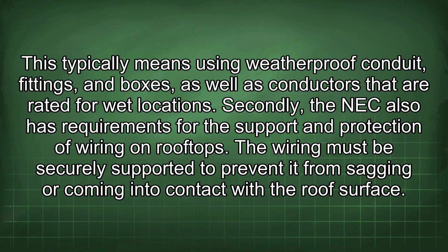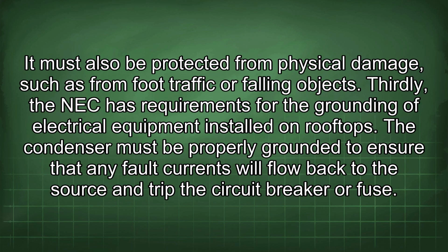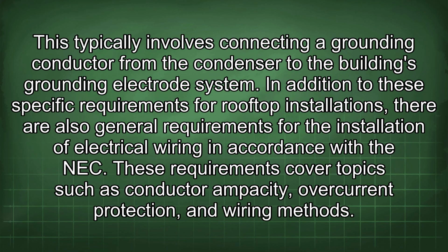Secondly, the NEC also has requirements for the support and protection of wiring on rooftops. The wiring must be securely supported to prevent it from sagging or coming into contact with the roof surface. It must also be protected from physical damage, such as from foot traffic or falling objects. Thirdly, the NEC has requirements for the grounding of electrical equipment installed on rooftops. The condenser must be properly grounded to ensure that any fault currents will flow back to the source and trip the circuit breaker or fuse. This typically involves connecting a grounding conductor from the condenser to the building's grounding electrode system.